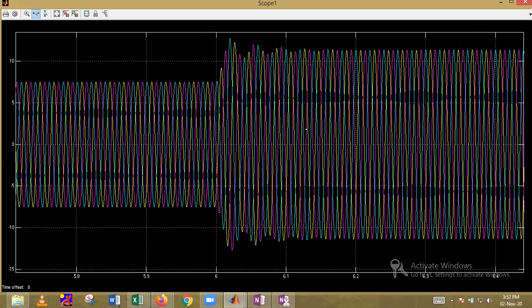Now you can see here at the 6 second mark, there is again a change in current because of another load which we are adding after 6 seconds. So my current will be more than 10 amperes. You can see here it will be around 11.6 or 11.7 amperes. So this is the effect of the load on the induction motor.